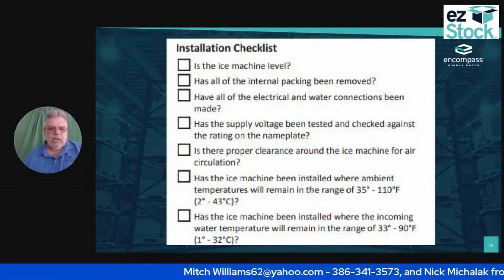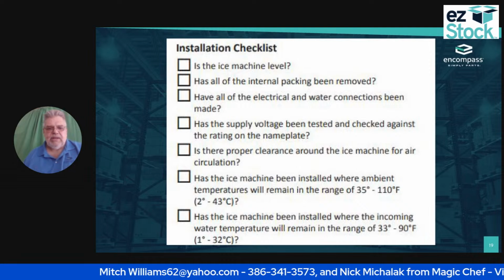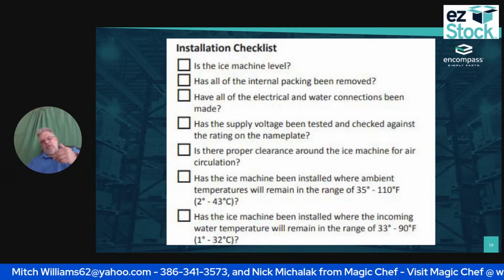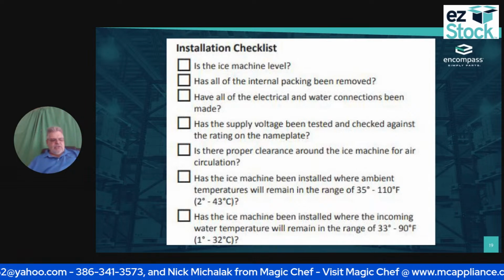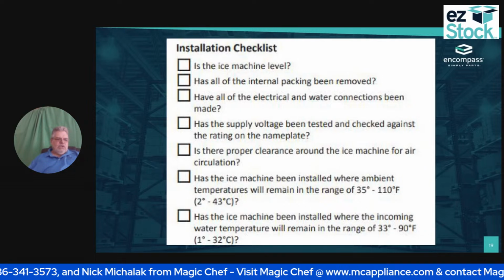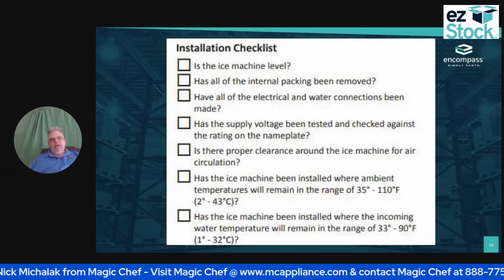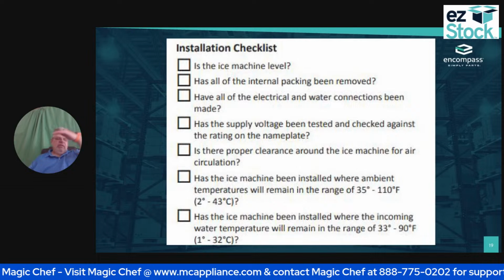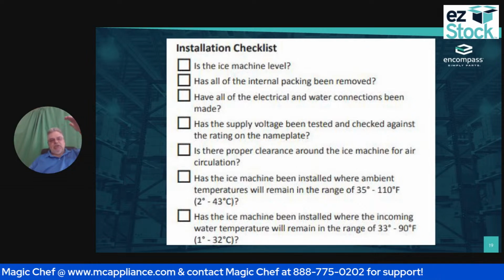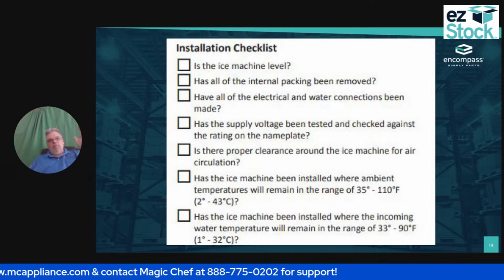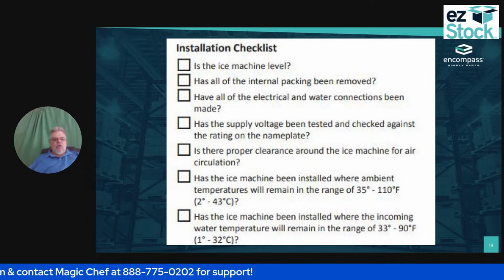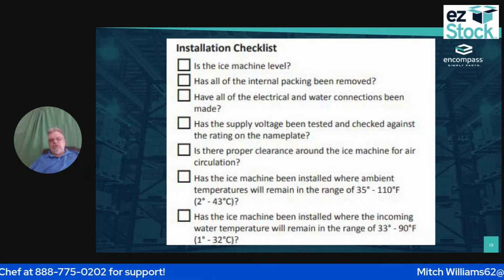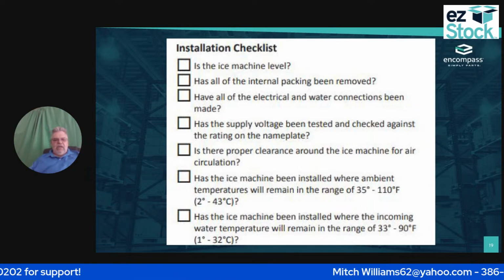Is there proper clearance around the ice machine for air circulation? I already told you about the restaurant slash bar where they put to-go boxes on top of the ice machine, and the cardboard boxes were so large they restricted the airflow and tripped it off on the high side.